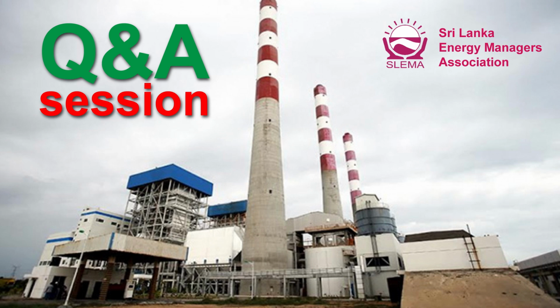What is the possibility of having a small coal power unit for auxiliaries alone? You mean running a power plant for auxiliary supply, right? That is what is being looked at the moment. But the problem is connecting the auxiliaries to a small power unit. This small power plant will have its own set of problems as well. It will have the same sort of reliability issues when connected to the grid. Any plant will have the same sort of grid instabilities, and perhaps frequency changes and all those kinds of things. So it's the same as having a 6 kV auxiliary supply.